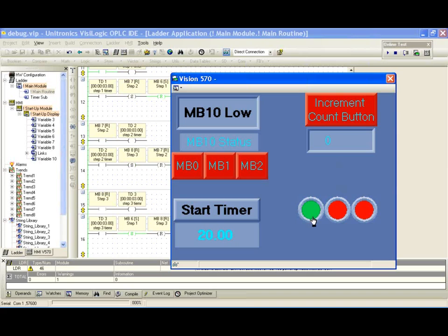So we see our first light, second light, third light, and first light again. Great. So we have gone through and looked at this application that we didn't have any knowledge of, and we've deduced 2 problems that we had. The first one was the variables all linked to the same bits. The second one was that the bit was just never being activated.